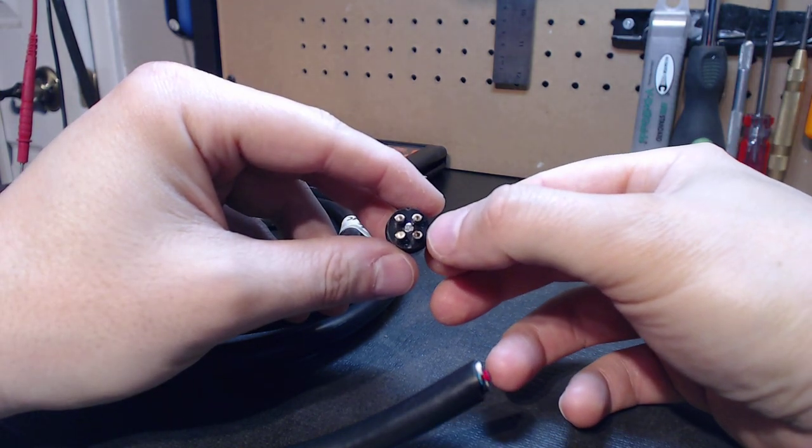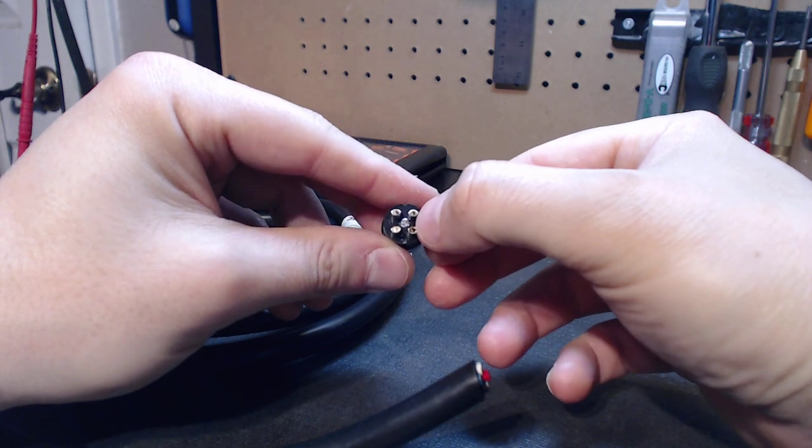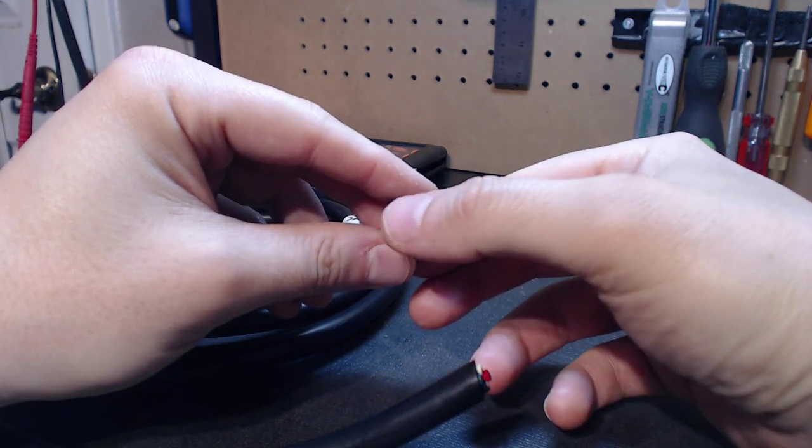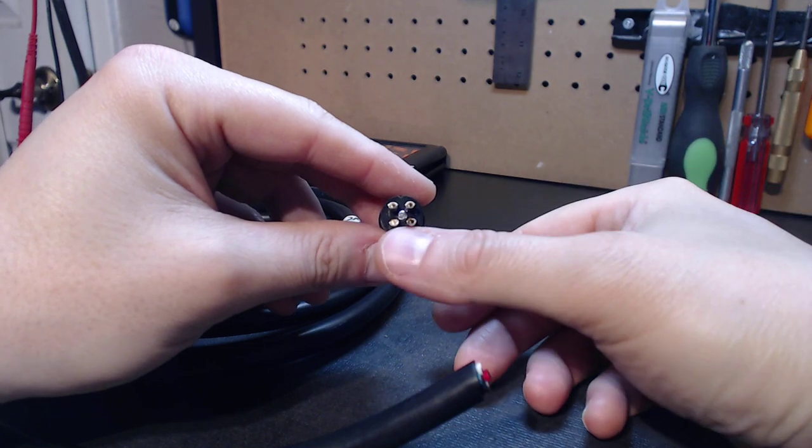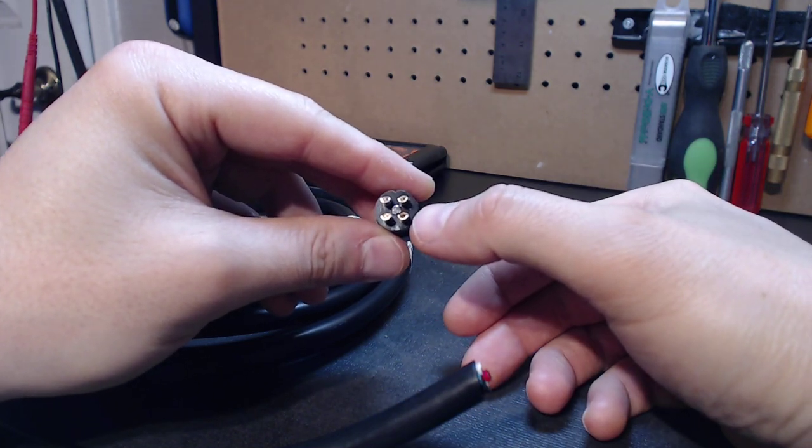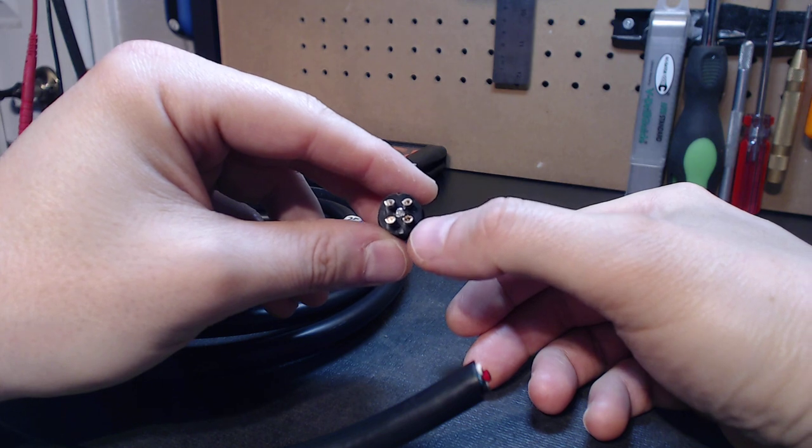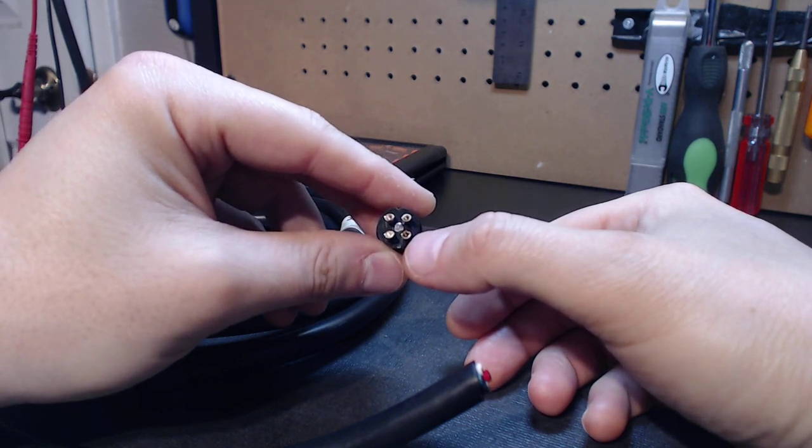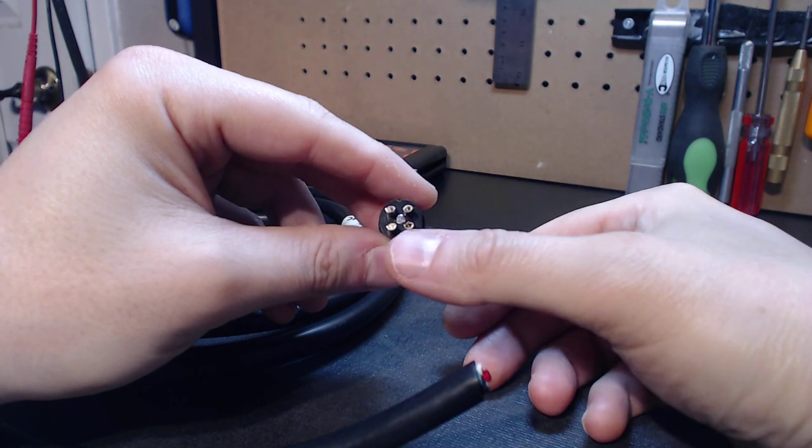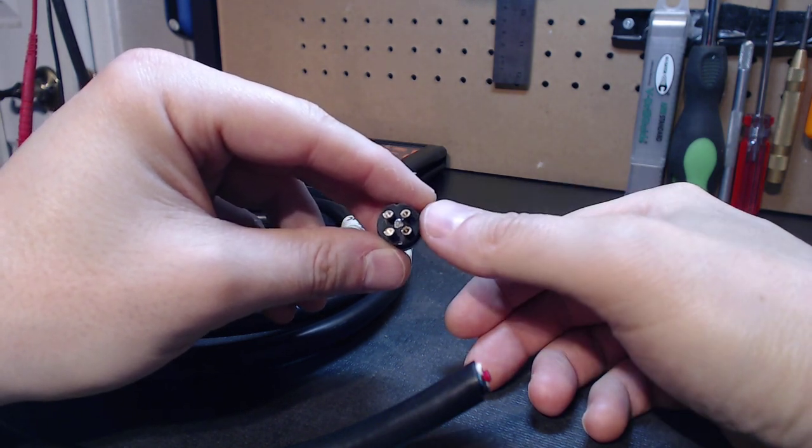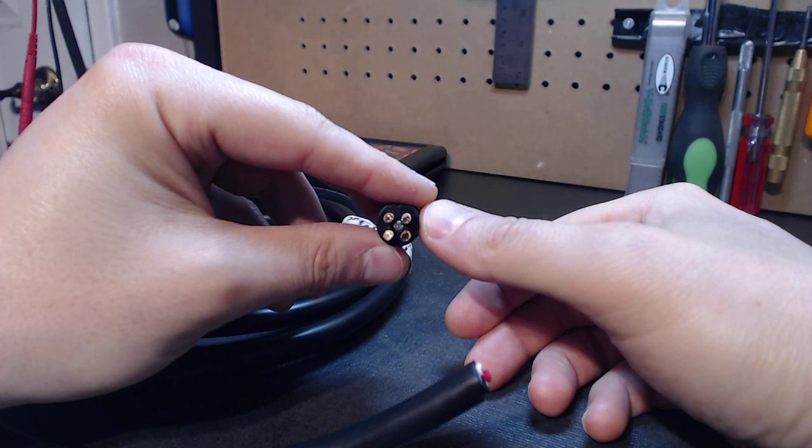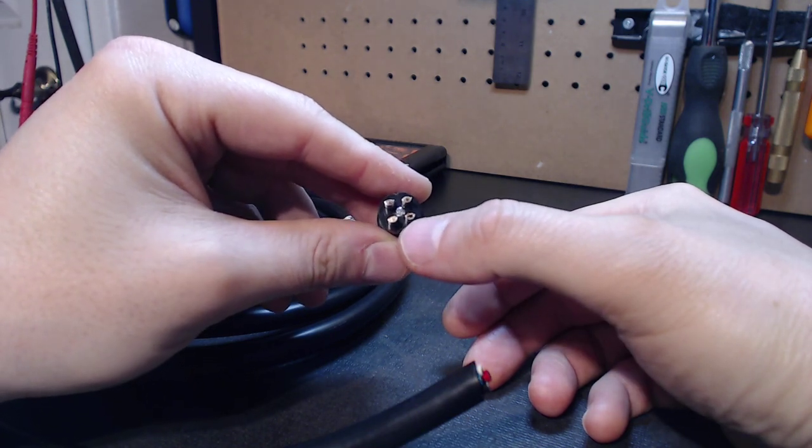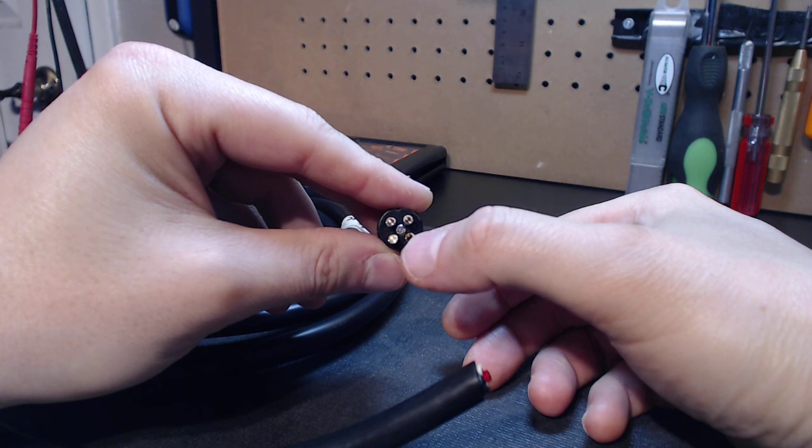Now when we're dealing with double shielded cable or shielded cable, you're going to have a drain. I get asked all the time, which end of the cable should I put the ground drain? Well, that's up to you. It'll work effectively on either end. I prefer the VFD end. I'm going to show you a cable, actually one of the two that I just built for a client.